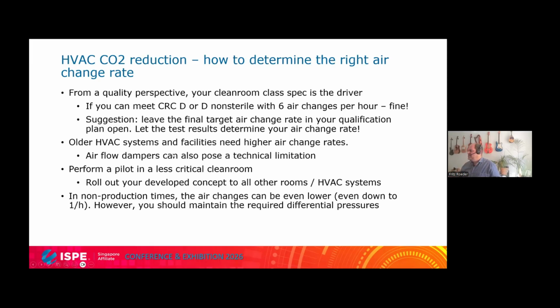Good. And my suggestion is, when you qualify the new air change rate, leave the target a bit open, make some studies, try out the recovery time or cleanup time as it's written in Annex 1 and look where you land. Then you don't need to start qualification again if you don't meet the number 6 or whatever. Make the target open and see where you land. Older HVAC systems need somewhat higher air change rates. They have higher pressure losses, more leakages, and the airflow dampers can also have a technical limitation. You just can't switch them down as much as you like. Good. Perform a pilot in a less critical clean room, wherever you like. Learn from it and then apply the same concept throughout the entire facility. This is how we have made really good progress, and that worked for us.